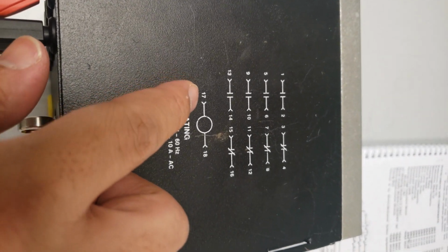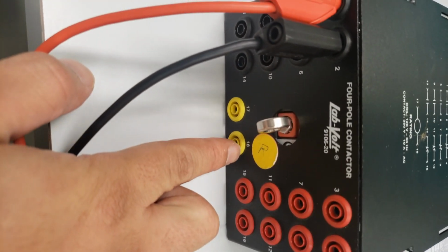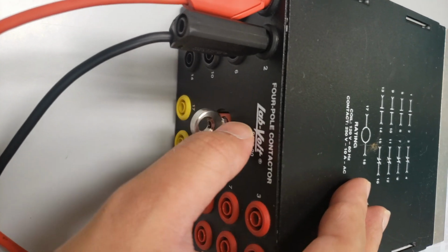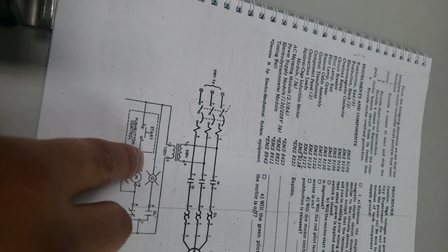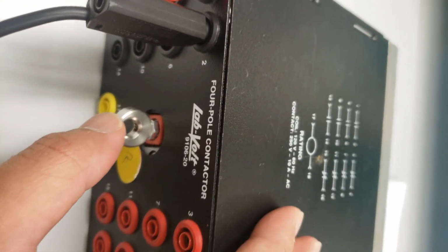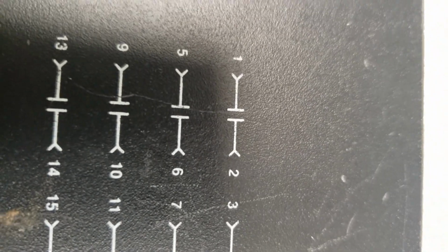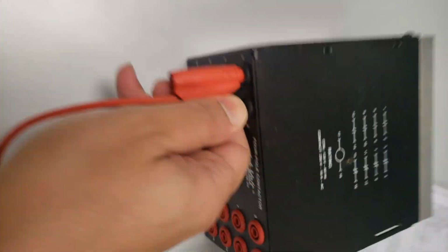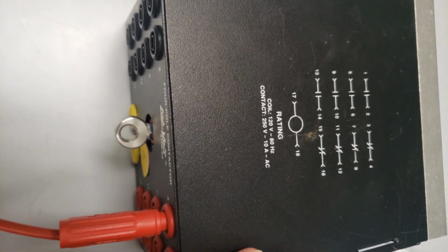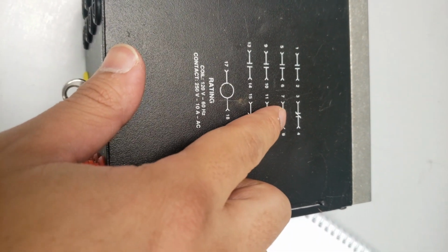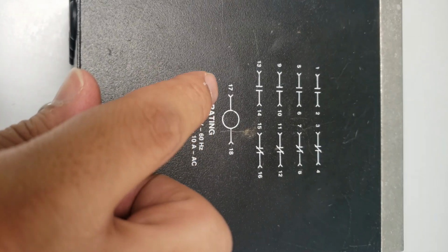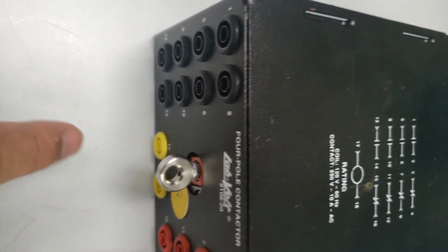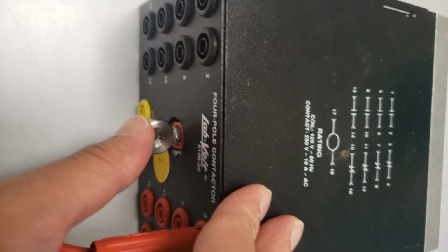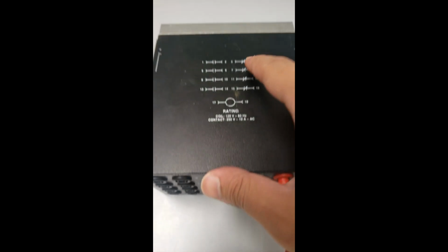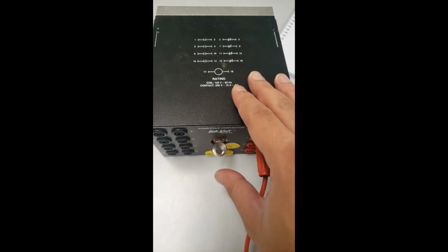There is no contact unless current passes through the coil, which is 17 and 18, and this one will go back. So if the current passes through the coil, this one will go back, and that normally open will be normally closed. The same if I use 3 and 4, it will be directly connected, because it's normally closed, and it will remain as it is unless current passes through the coil 17 and 18, and this one will go back, and if this one goes back, this one will be normally open and the sound will not appear.